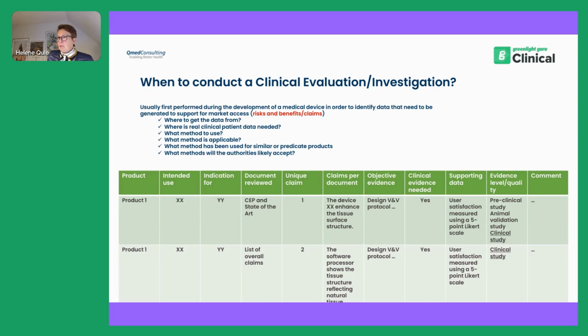So again, I'm a big fan of tables, and I'm really a big fan of trying to map out, to be sure that I have all the claims mapped out. I have defined my safety and performance and clinical outcome parameters. I have defined my claims. Now I need to find out in which documents, because there could be different levels of documents where the different claims could collect data to support that, and make sure that when you move on to the clinical study, I always work with these table formats where I list out the different claims and make sure that there is a red thread between the intended use, indication for use, all the way to the claim, and where in the documentation I can find the data to support my claims.